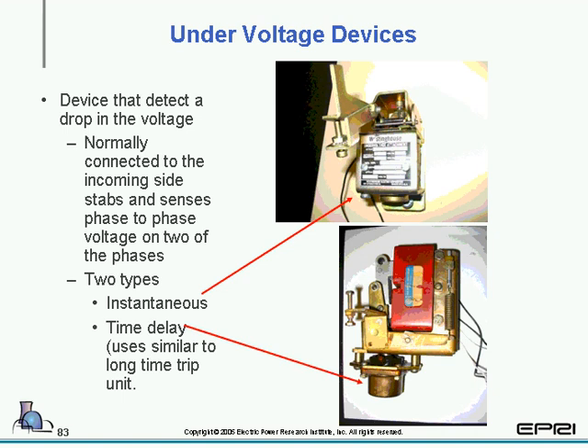Undervoltage devices, the devices that detect a drop in voltage, are normally connected to the incoming side stabs and sense phase-to-phase voltage on two of the three phases. And we have two types. We have instantaneous, which is the Westinghouse on the upper picture. And then we have a time delay, which you can see by a small little dash pot located at the bottom of the undervoltage device, which means that this breaker could see below the rated voltage, or whatever the undervoltage is set up for, for a specific amount of time without tripping the breaker.